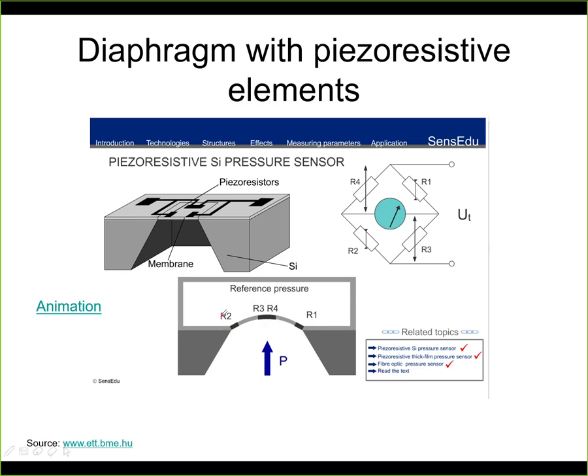Now those sensors, those strain gauges, are typically connected in a bridge circuit. We have discussed bridge circuits when we were talking about force sensors. So here is the schematic. We have 4 sensors like this. You can see that 2 of them are measuring compression. So R1 and R2 in this case measure compression, and R4 and R3 measure tension. So we can read the output voltage, which is a function of the deformation. And this principle is basically used in all of today's pressure gauges with electrical output. Some of them have a diaphragm, some of them have a slightly different configuration, but in all cases we measure the deformation of something.